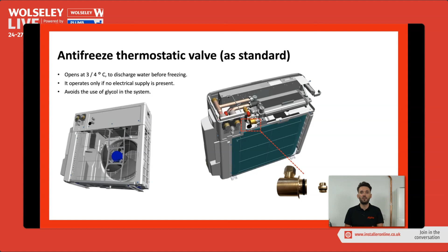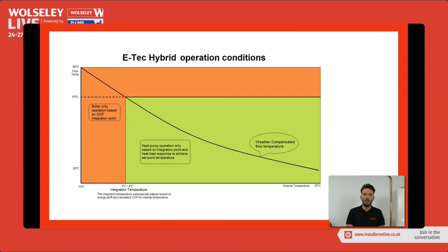So we've been a bit clever. We've limited the flow of the heat pump at 55. So if we're ever asking for a flow temperature of over 55 degrees, we're going to use the boiler because that's where the boiler's more efficient. However, when we're looking at lower temperature heating, maybe on a milder day, sort of 7 degrees outside, we can utilise the heat pump then and run the system at a lower flow temperature. And again, like I said earlier, it works on a COP calculation, so it works out the efficiency of the heat pump, the efficiency of the boiler, and it will always choose the cheaper appliance.